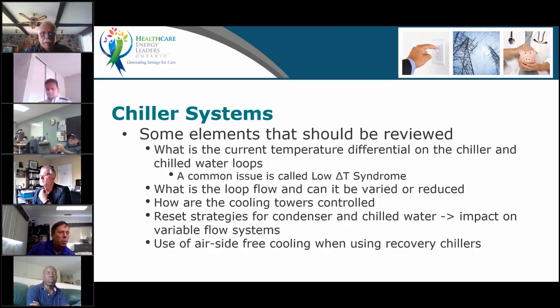If you've got variable flow and you reset your chilled water, that means you're sending warmer water through your system because you reset it. So the space temperature or the coil sensor sees that, hey, the water's warmer, I need more flow, I'm going to open the valve. If I open the valve, the pump speeds up. So yeah, you're saving chiller kWh, but you're increasing your pump kWh by doing that reset. So when you do those kinds of strategies, always look at the big picture. Otherwise, you may end up paying more, which is possible actually when you do chilled water reset on a variable flow system.